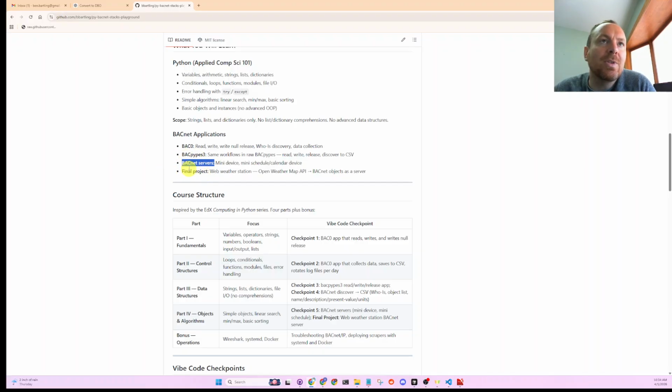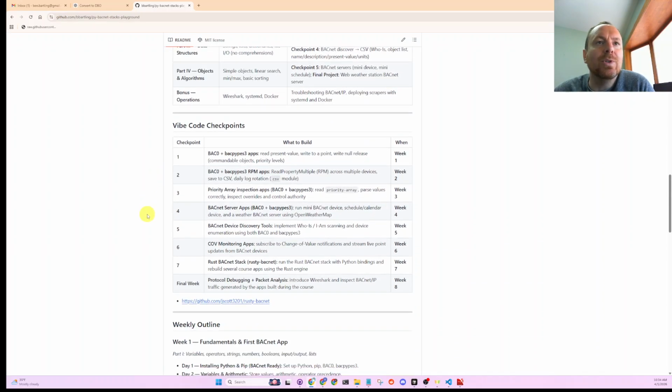We made a script that exposes the web weather data as a little BACnet device, and you can discover the points and see web weather dry bulb, relative humidity and temperature, which is actually a cool real life application, like we talked about before. Building automation sensors are pretty flimsy, so if you can control your building HVAC to airport weather station data, which is probably where OpenWeatherMap pulls the data from, it might be better sensors. So it's kind of fun to play around with.